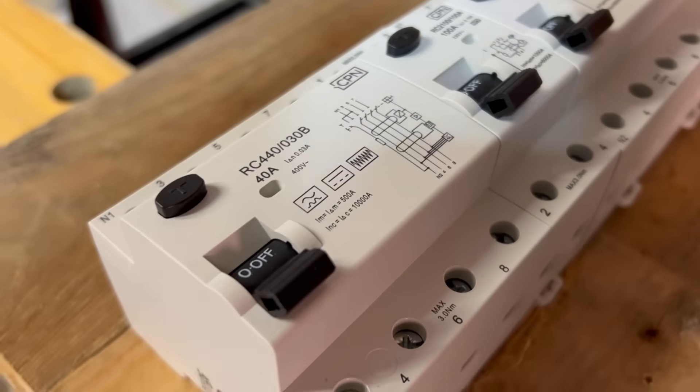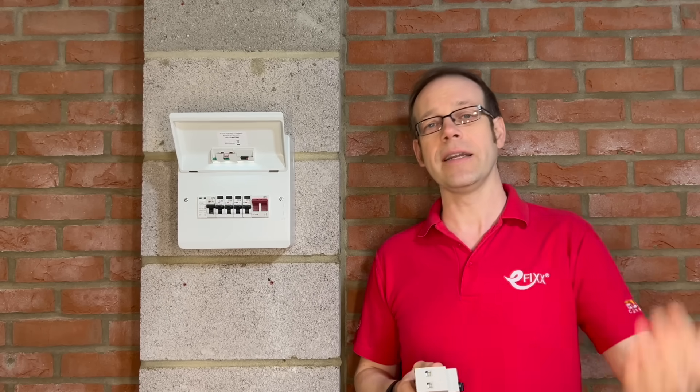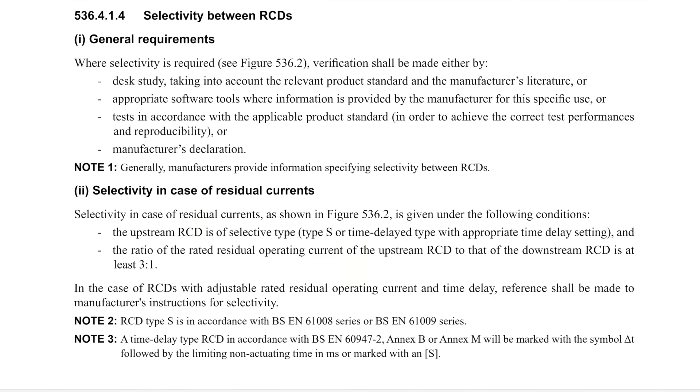However, this time delay by itself is not enough to prevent both devices tripping in the event of a fault as it's likely to hold off tripping for a matter of milliseconds rather than seconds. So to achieve proper selectivity it must also comply with the second part of that reg.